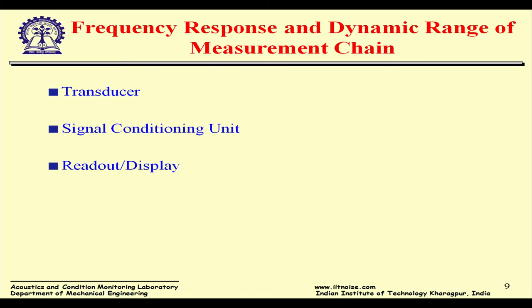I've been to industries where people give me numbers. Sometimes they did not even know when this instrument was calibrated, or what the units are, because they have a value X on the shop floor. They are reading with X value. Now at X plus 20 it is time to get an alarm, but they do not know what the unit of this X is. Okay. So as engineers, we need to be careful about these aspects as well.